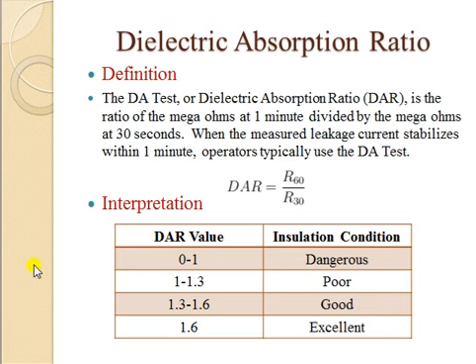The first time resistance test is called the dielectric absorption ratio, or DAR. What you do here is take insulation resistance for 60 seconds and for 30 seconds, and take the ratio. DAR equals insulation resistance at 60 seconds divided by insulation resistance at 30 seconds — R60/R30. Some equipment nowadays give the direct value of DAR on its digital screen. The interpretation per IEEE standard: DAR 0 to 1 is dangerous, 1 to 1.3 is poor, above 1.3 starts to be considered good, and 1.6 is an excellent value.